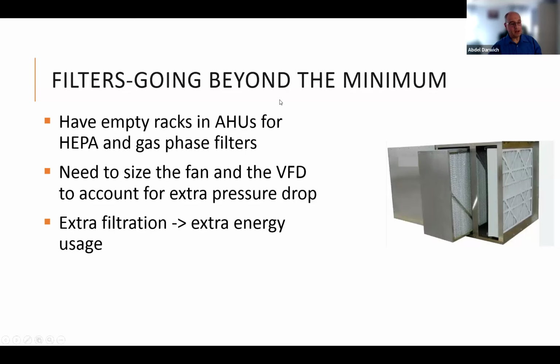If you want to go beyond the minimum, what we are doing now in some of the projects that I am designing, in an AHU, which is the air handling unit, the central AC unit in the hospital, is leaving empty racks to put in HEPA, which is really high level filtration. It's even higher than MERV. It will stop particles down to PM1 even. And gas filters. Because these have high pressure drop, they consume energy. We don't usually put them there if you don't have wildfire smoke, but we have the racks ready, and the fans are strong enough to handle this in the future.